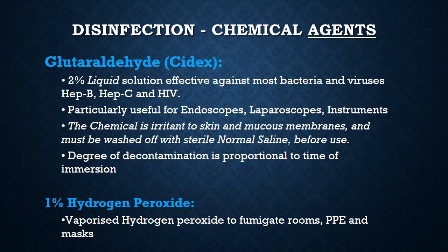2% glutaraldehyde, or the trade name Cidex, is one of the commonest used liquid chemical disinfectants in hospitals, and it is effective against most of the bacteria and viruses, especially hepatitis B, C, and HIV. This is particularly useful for dipping endoscopes and laparoscopes and other instruments, and generally 15 to 30 minutes are enough for the instruments to be decontaminated. But please remember, first the instruments are washed, then placed in the glutaraldehyde solution.